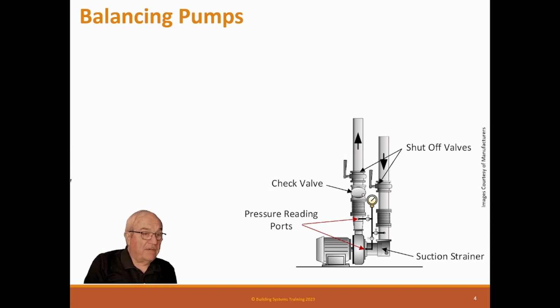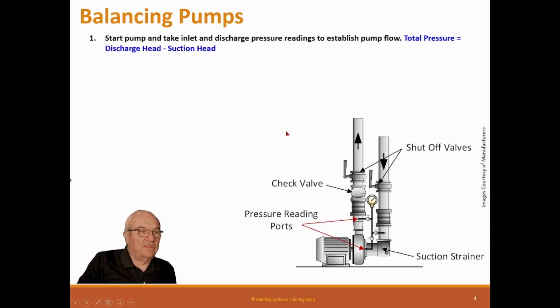They're not very well made. They're not manufactured correctly for the service, and I would never ever use one. And I know this by experience because I have spent hours with a big wrench and a big pipe on a cheater bar, taking hours to open a valve or close a valve. So basically, don't ever use them for a close-off valve. If you've got to use them for anything, I guess a check valve, but why would you? They cost three or four times more than a check valve. So, okay, I'll get off my soapbox. Don't use triple duty valves.